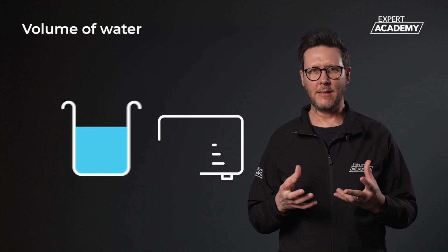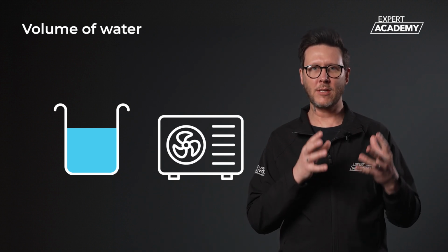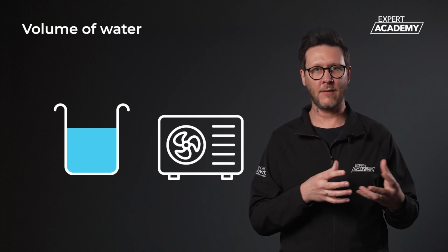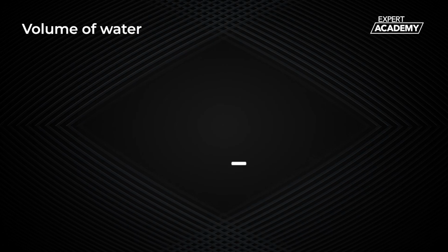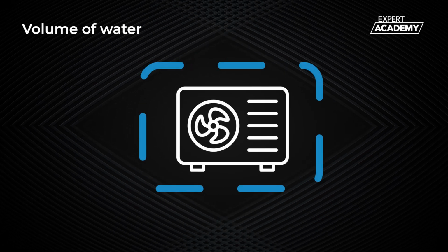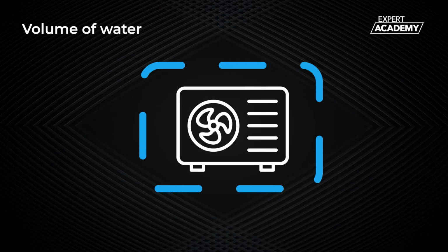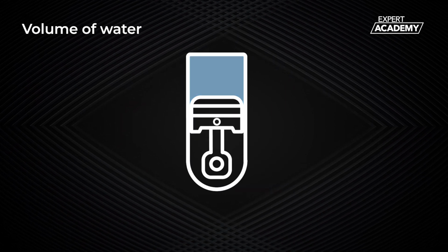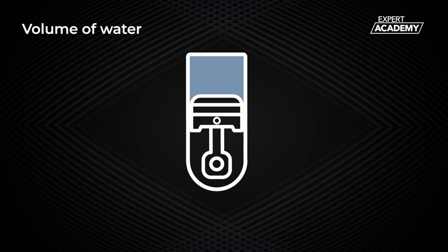What we mean by this is any water that is always available to the heat pump that is not closed off by things such as zone valves and thermostatic radiators. This allows the heat pump to freely circulate the minimum water volume as and when it requires. A sufficient volume helps to prevent the frequent cycling of a heat pump compressor.